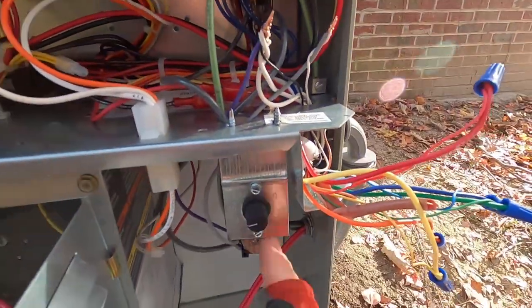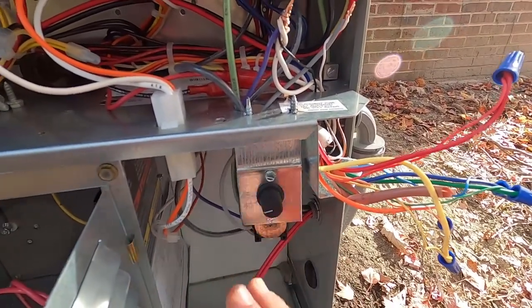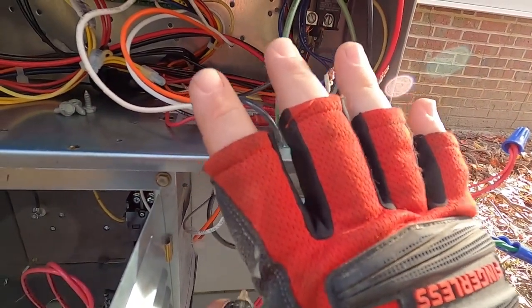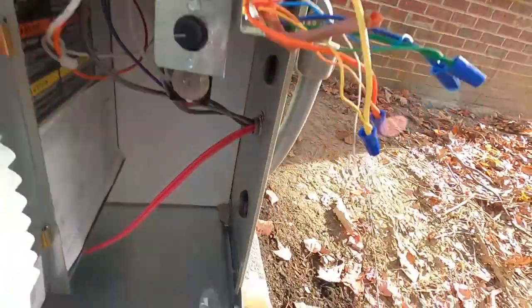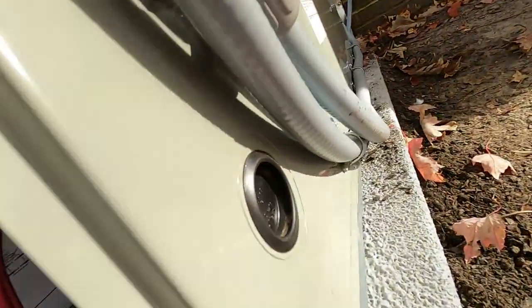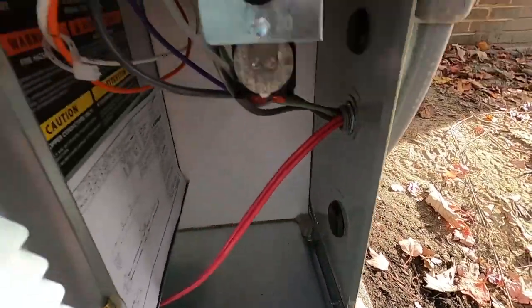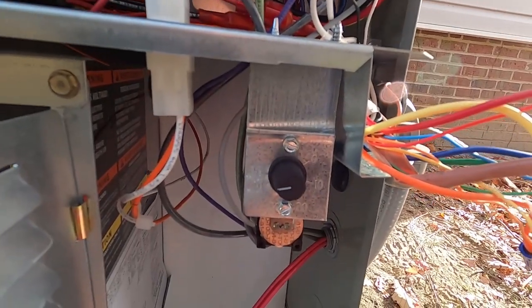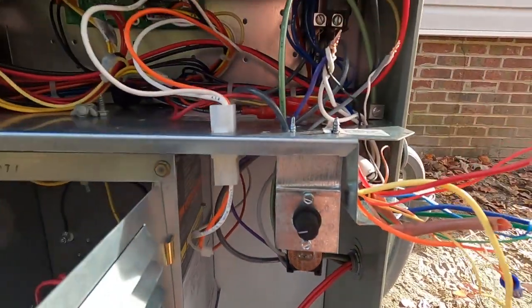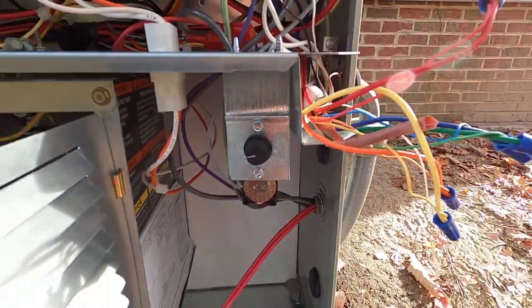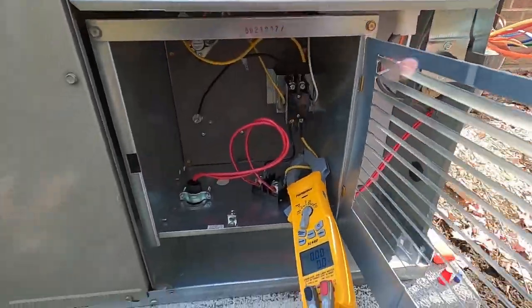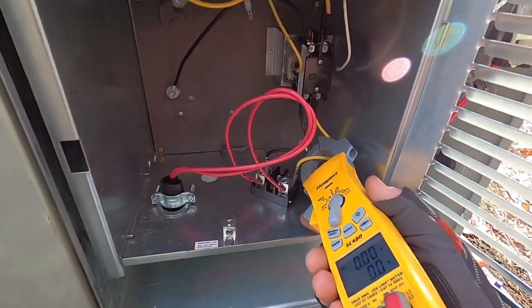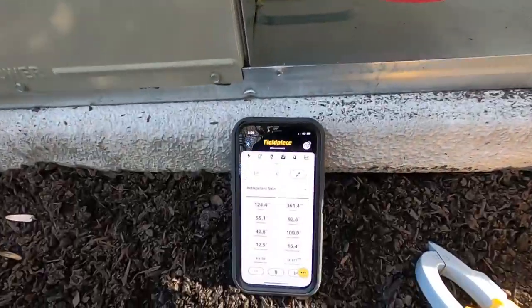So I'm going to come back and replace this one so I don't have one reading the temperature inside this cabinet and not closing when it needs to. And then this little plug on the side of this unit, I'm going to pop a little hole in it. And then I'm going to run the thermocouple for that switch out here, so it's sitting outside reading our actual outdoor temperature, and make sure that when it does get cold enough that the auxiliary heat is needed for this unit, they come on like they're supposed to, and we don't end up with a service call or a recall on an install job. But everything here is working, guys.